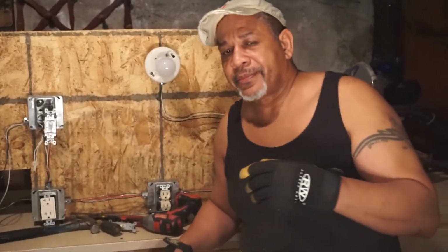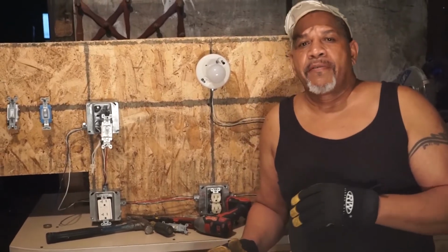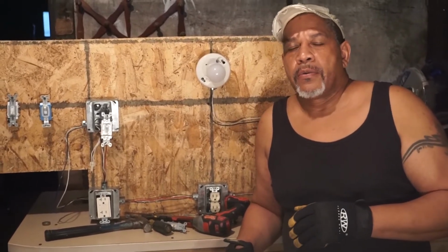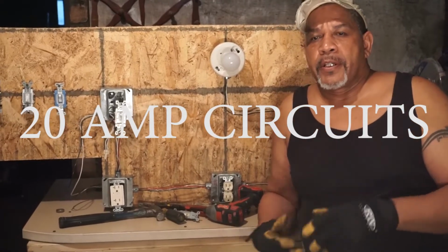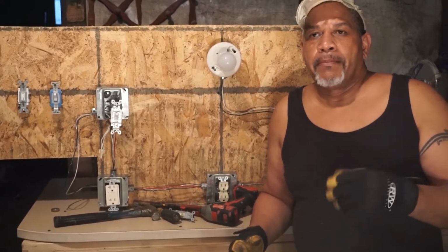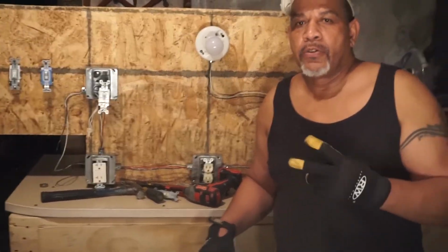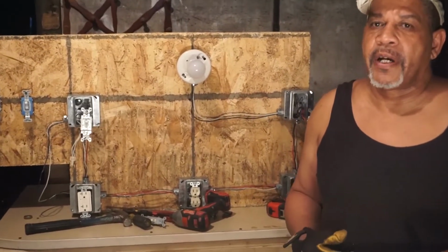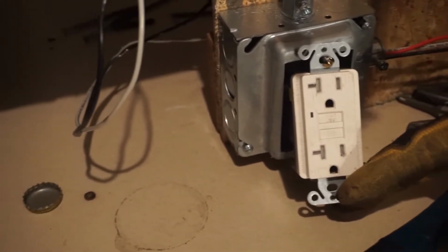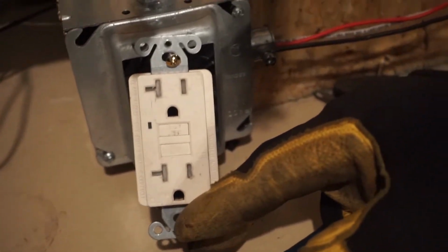In your kitchen, you're supposed to have two 20 amp services, though that doesn't always happen because you can be grandfathered in with old circuitry. That does not include your dedicated circuits, which we'll get to in a minute. Both of the two 20 amp circuits should be GFCI controlled, which is ground fault circuit interrupter. Most of us call it a GFI. They're the same thing.